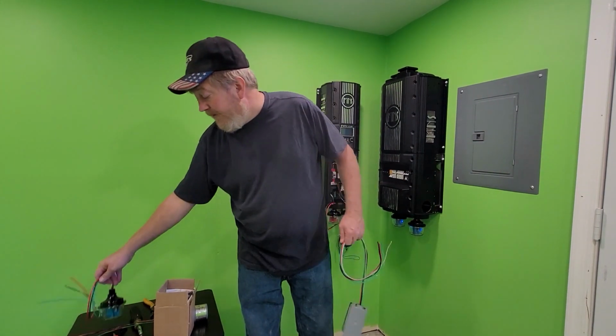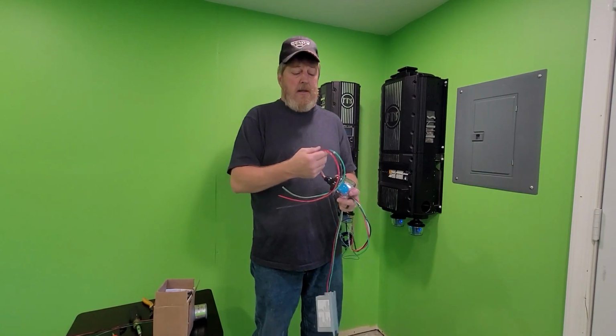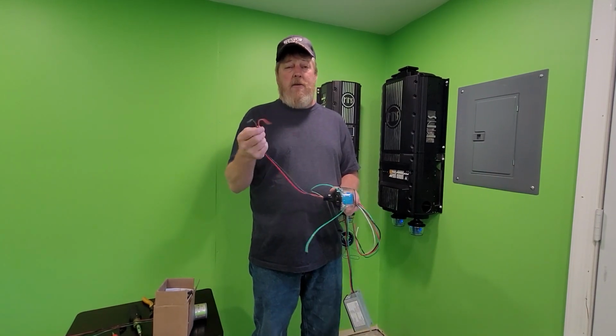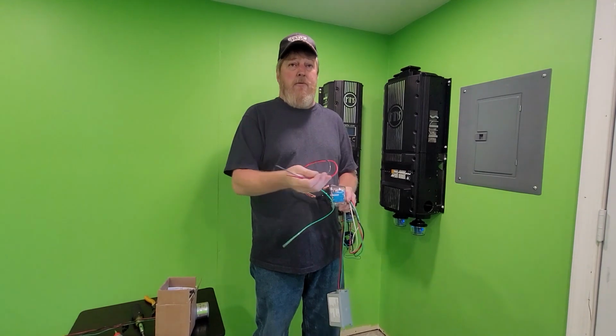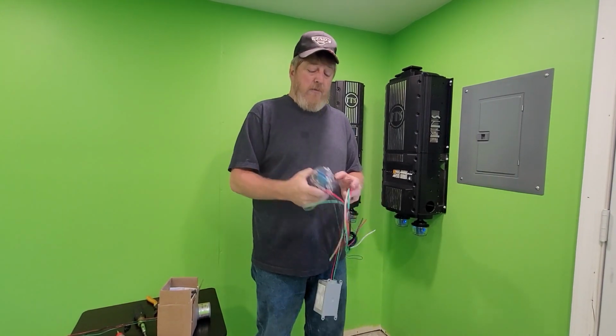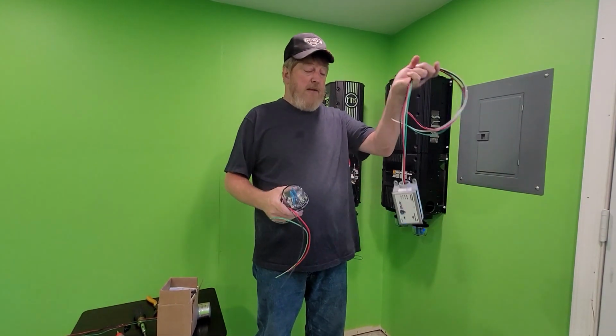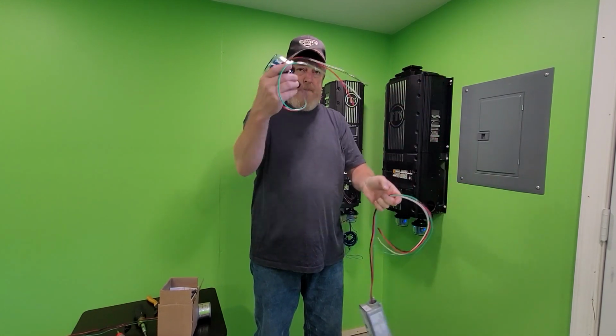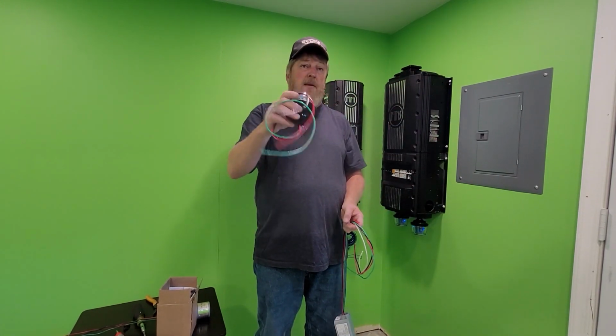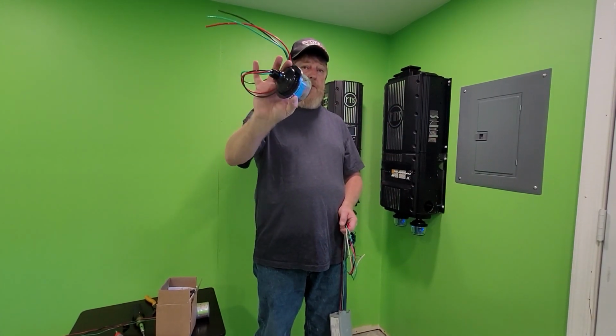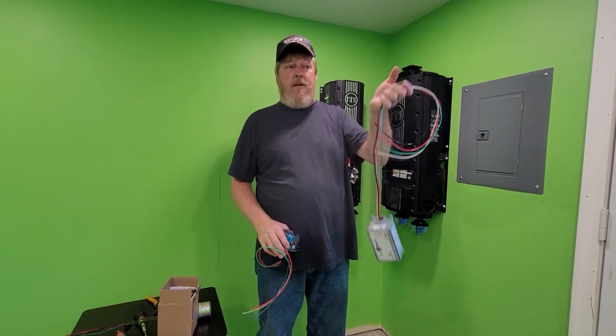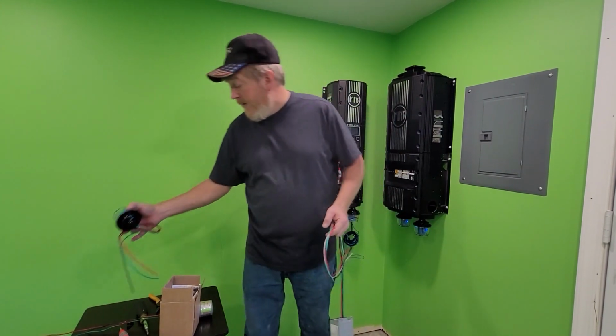So in a sub panel, you really do want to protect that neutral. What I do is use a second SPD and put my black wire on the neutral, and sometimes even my red wire. I'll use an extra one of these. Remember, I said I think we paid about $400 for this - we paid about $90 for this. So for $180, I can get 2 of these, and I still have about $220 left in my pocket.